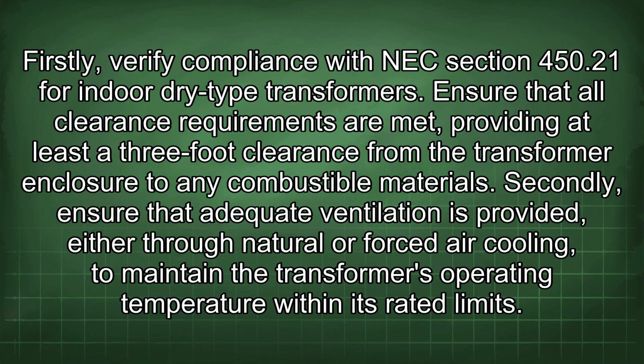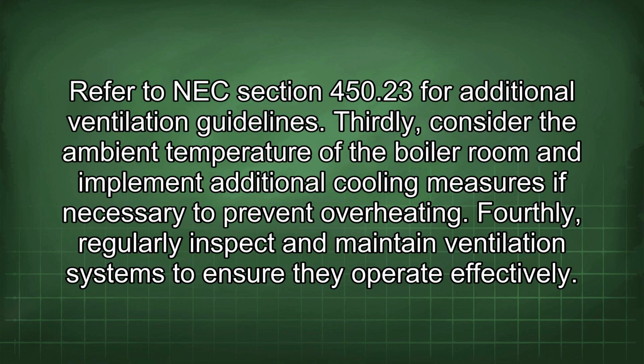Firstly, verify compliance with NEC section 450.21 for indoor dry-type transformers. Ensure that all clearance requirements are met, providing at least a 3-foot clearance from the transformer enclosure to any combustible materials. Secondly, ensure that adequate ventilation is provided, either through natural or forced air cooling, to maintain the transformer's operating temperature within its rated limits. Refer to NEC section 450.23 for additional ventilation guidelines. Thirdly, consider the ambient temperature of the boiler room and implement additional cooling measures if necessary to prevent overheating.